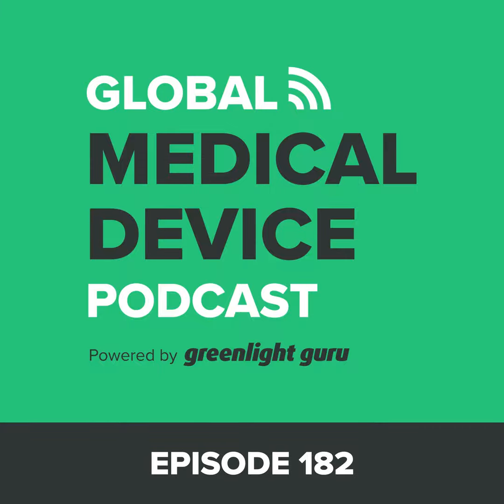If you're looking at a full quality system, what do I do? QSIT is good, but QSIT focuses on a few areas, the heavy hitter areas that FDA would come in and hit during a quality system inspection. It'll certainly cover the bulk of where you might have exposure in the quality system. But if you want to really see where all the details are and where the full quality system is laid bare and presented in a way that you can develop action items on across the entire set of processes, I'd encourage you to go to that MDSAP audit approach, even in preparation for an FDA inspection. It's a really good idea.